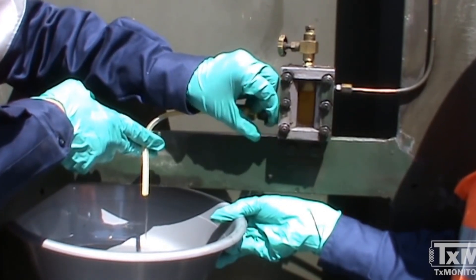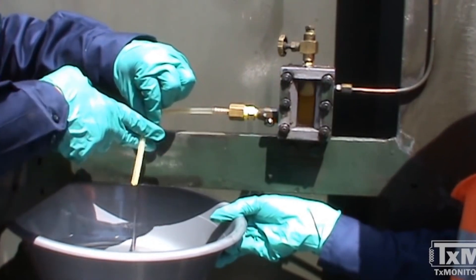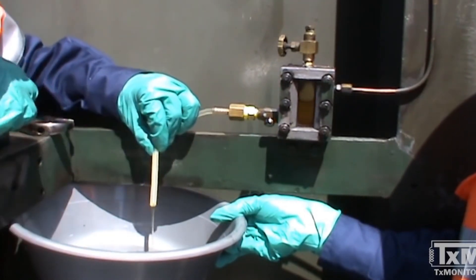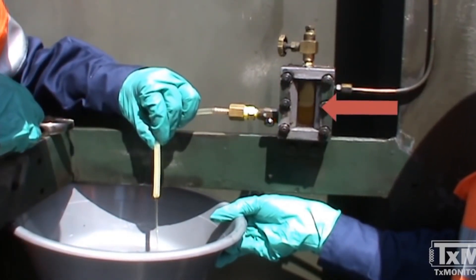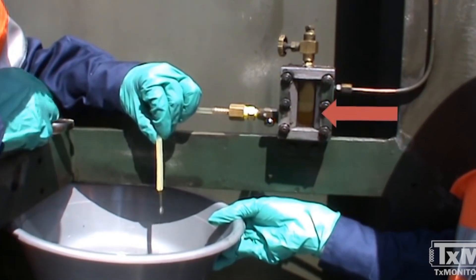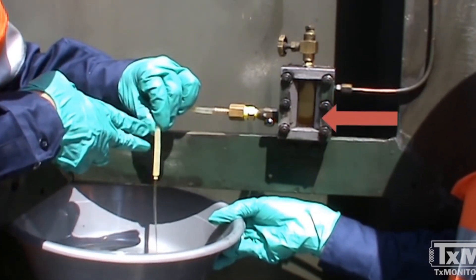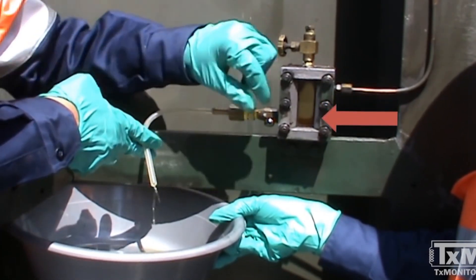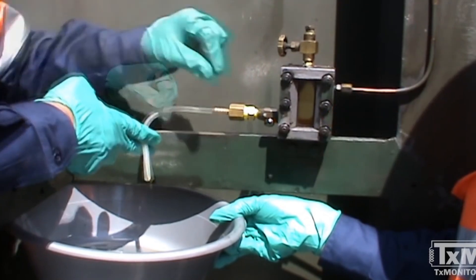Open the bottom port of the sampling device and allow the oil to drain. You will notice that the oil level in the sampling device decreases. Once the sampling device is full of gas, close the bottom port.